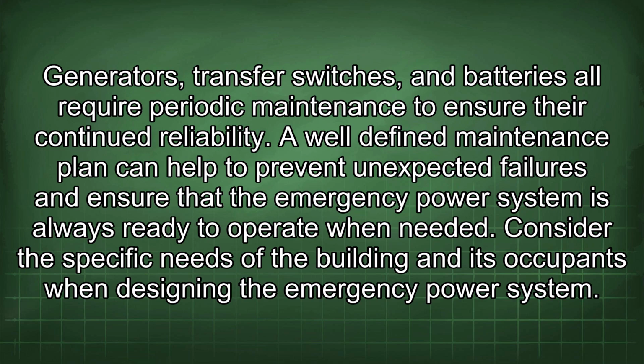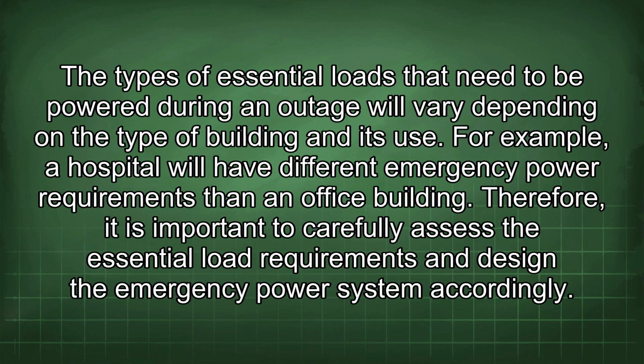Consider the specific needs of the building and its occupants when designing the emergency power system. The types of essential loads that need to be powered during an outage will vary depending on the type of building and its use. For example, a hospital will have different emergency power requirements than an office building. Therefore, it is important to carefully assess the essential load requirements and design the emergency power system accordingly.